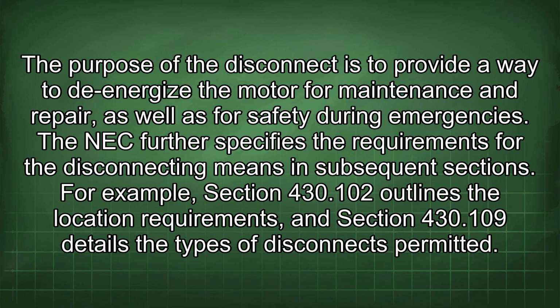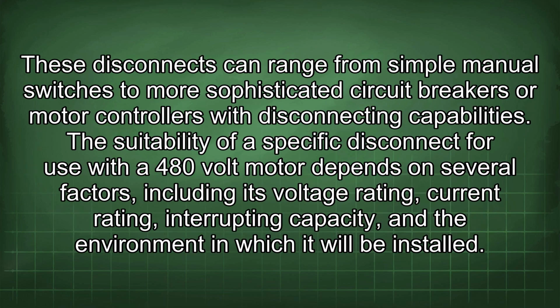The NEC further specifies the requirements for the disconnecting means in subsequent sections. For example, Section 430.102 outlines the location requirements, and Section 430.109 details the types of disconnects permitted. These disconnects can range from simple manual switches to more sophisticated circuit breakers or motor controllers with disconnecting capabilities. The suitability of a specific disconnect for use with a 480-volt motor depends on several factors, including its voltage rating, current rating, interrupting capacity, and the environment in which it will be installed.